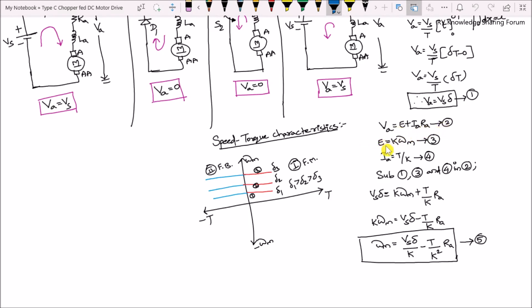The back EMF of a DC motor is E = K·ωM (equation 3), and the armature current is Ia = T/K (equation 4). Substituting equations 1, 3, and 4 into equation 2 gives VS·δ = K·ωM + (T/K)·Ra. Rearranging yields the speed-torque relationship: ωM = (VS·δ)/K − (T·Ra)/K². This is equation 5, which is the speed-torque relationship of a DC motor drive fed by a DC chopper.